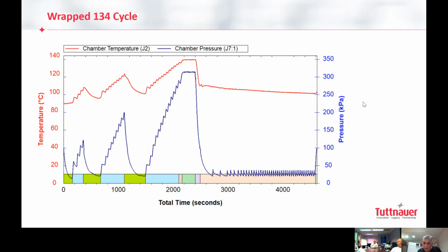So no deal. We have to look for a solution. We will go for the second level vacuum pump, where they are able to remove without any problem 80% of the load, of the air, sorry. So then every simple pump, not simple, but the one we are using, the membrane, because don't forget that this is a plug and play machine. You can't use the type of water ring vacuum pump or etc. like the HSG, if you know, or the bigger model. This is very difficult, this is a different concept of vacuum pump, which is using a lot of water, utilities, then no deal. So we are going for an air vacuum pump, membranes.